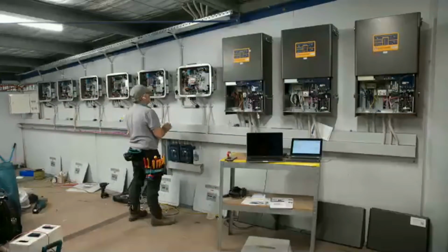They're very easy to commission. I was extremely pleased with the process, and also the documentation from Selectronic, because these are managed AC coupled inverters — meaning the Selectronic converter has a comms cable, RS485, connecting to all those ABB inverters and directly power controls them. It's important in an off-grid situation that if you've got AC coupling, you have a way to throttle back your solar inverters whenever the battery's full and the loads are light. So you've got to control them very fast too — millisecond response time with managed AC coupling.